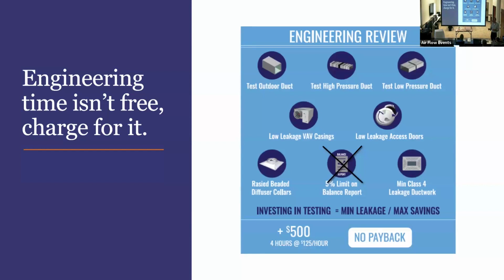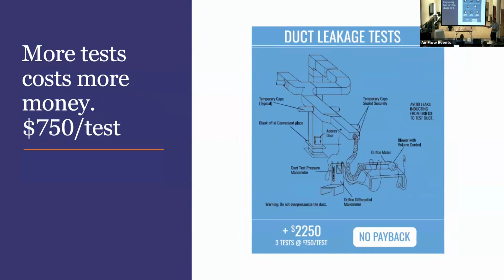It's gonna take more engineering time, so when you turn in your fee, make sure you've got some extra time there to make sure that the contractor does, and that the balancer does, all those things, right? There's no payback for the owner yet. Add 3 more pressure tests. A pressure test is about 750 bucks worth of horsing around. If you use life safety dampers that don't leak through the sleeve, you're gonna get these tests back anyways. This can be a free thing.